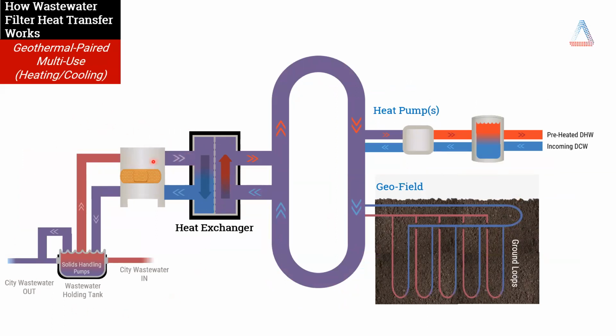You can take energy from wastewater, put it into the field and the loop when that energy level is starting to decline, or when the field and the loop are starting to gain energy and overheat, you can take that and reject it into the sanitary sewer, having a really great effect to stabilize the field, as well as supplement energy into and out of the overall system, extending the operational parameters of your downstream equipment.